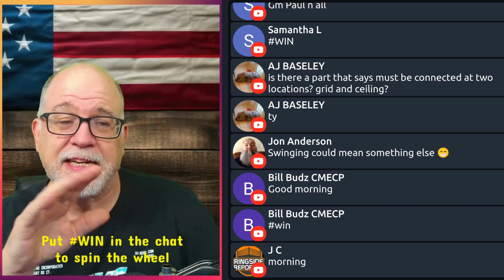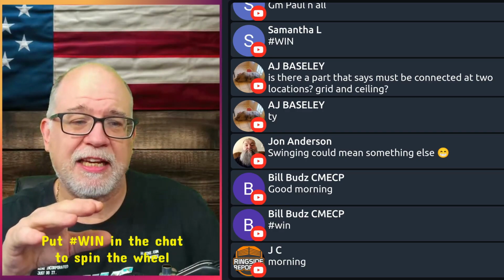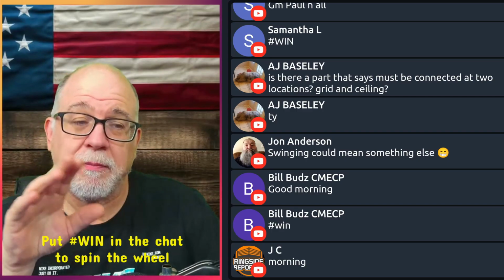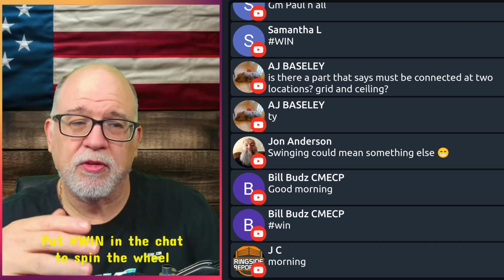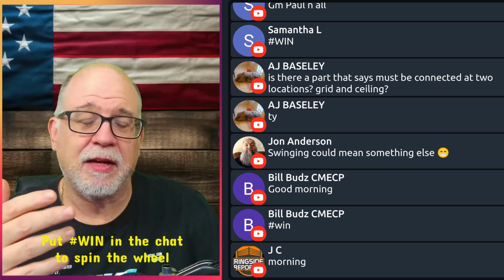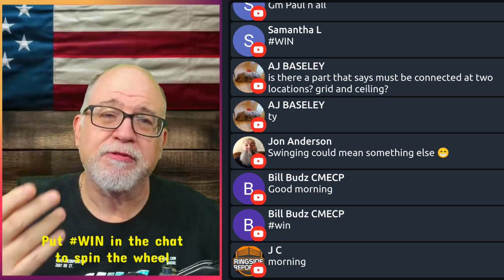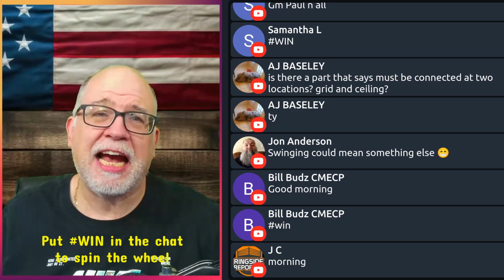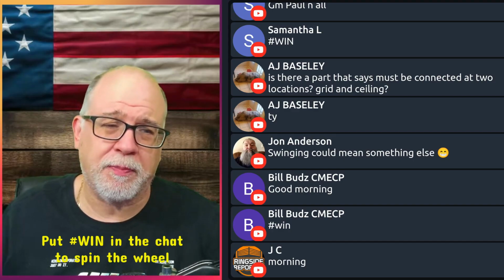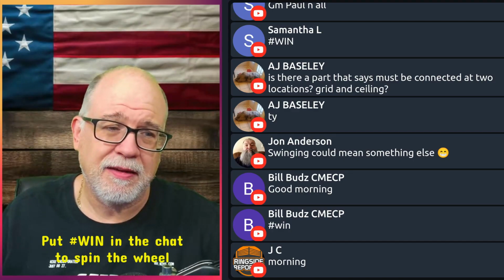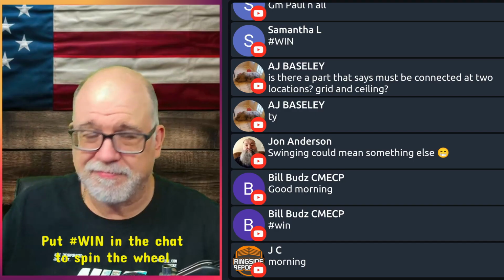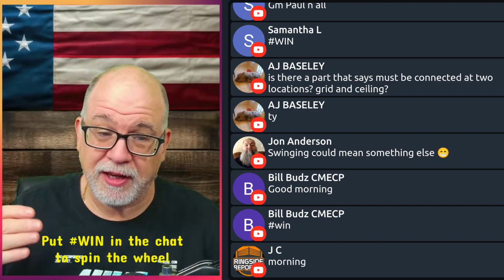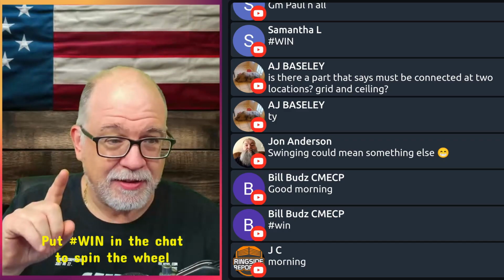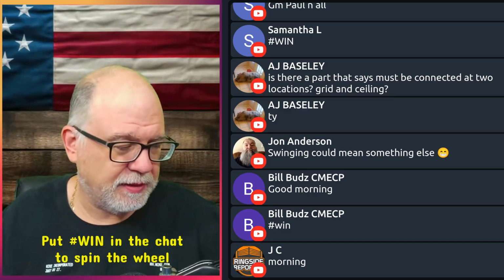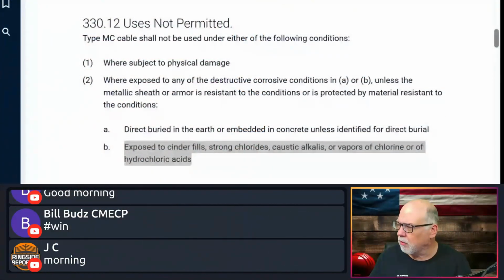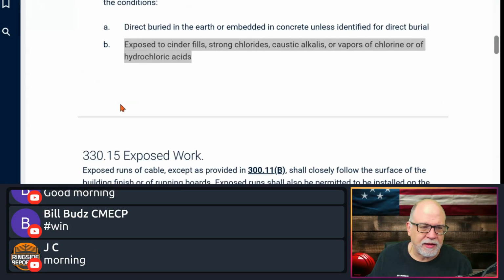In fact, the test that I did for 18 months, I immersed PVC jacketed MC and regular MC in a chamber that was filled with hydrochloric acid, and it was heated up outside to allow the vapors to circulate for 18 months. The PVC jacketed MC looked brand new when you stripped off the PVC. Did nothing to the PVC. Okay? Now, the regular MC, totally trashed, but not the PVC jacketed MC. It looked great. Okay? So, anyway, enough of that. But again, we make a product like the PVC jacketed that does that.